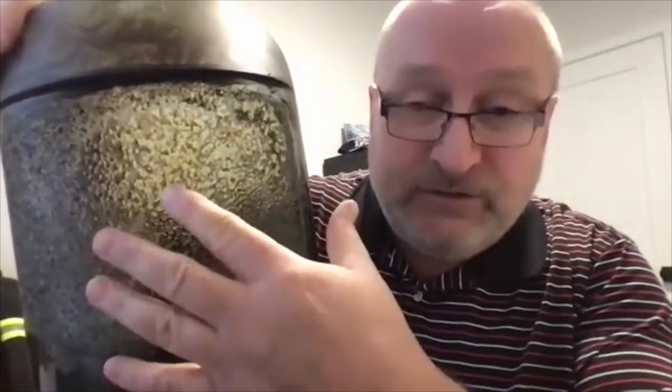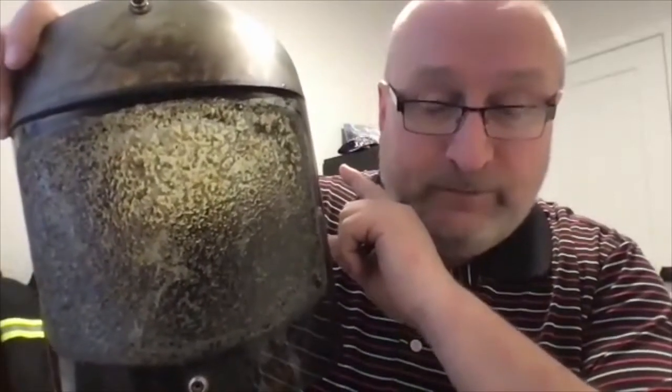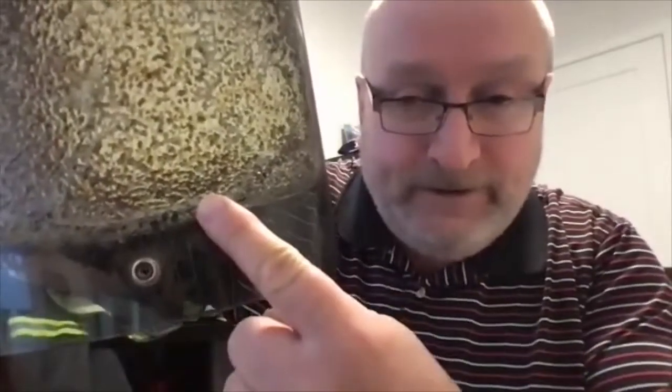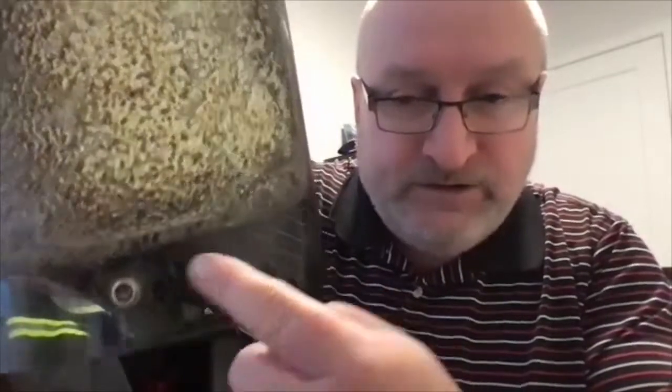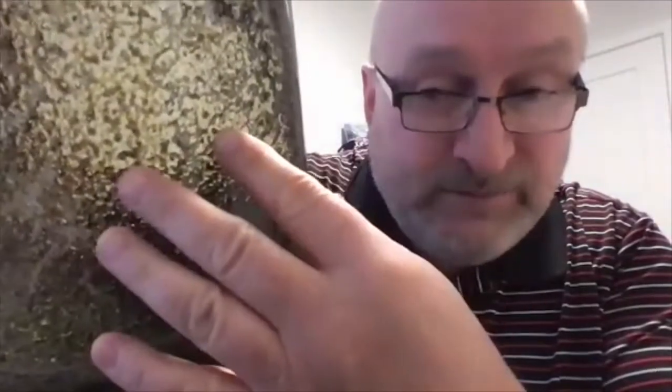So this PPE — what it's doing is it's taking the heat from the arc flash incident energy so that your skin will not receive any more than the 50% probability of a second degree burn injury. So the cool thing here is where the arc flash cloth was — the PPE — you can see that the plastic is still clear, it's brand new. Where the worker has to see, this has to be exposed.